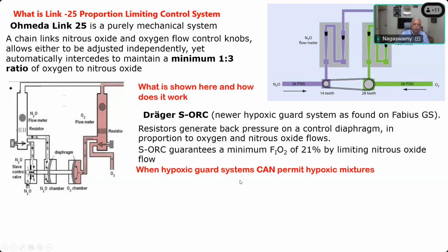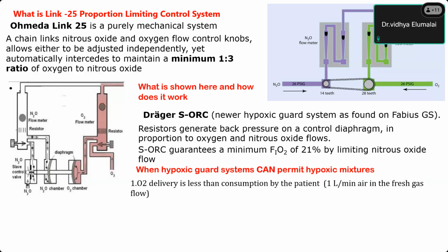When can hypoxic guard systems permit hypoxic mixtures, even though they are incorporated to prevent hypoxic delivery? What conditions can still allow a hypoxic mixture to be delivered in the presence of a hypoxic guard system? The flow meter is damaged or broken. When the oxygen delivered is less than the consumption by the patient.